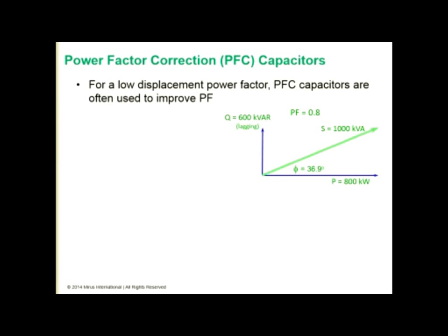So we typically will address a low power factor by applying power factor correction capacitors. But this is effective only with respect to displacement power factor. In our power triangle shown here, we have a power factor of 0.8, which has a real power of 800 kilowatts. Our inductive reactive power is 600 kvar. And the apparent power, the sum of the two vectors, ends up being 1,000 kVA.